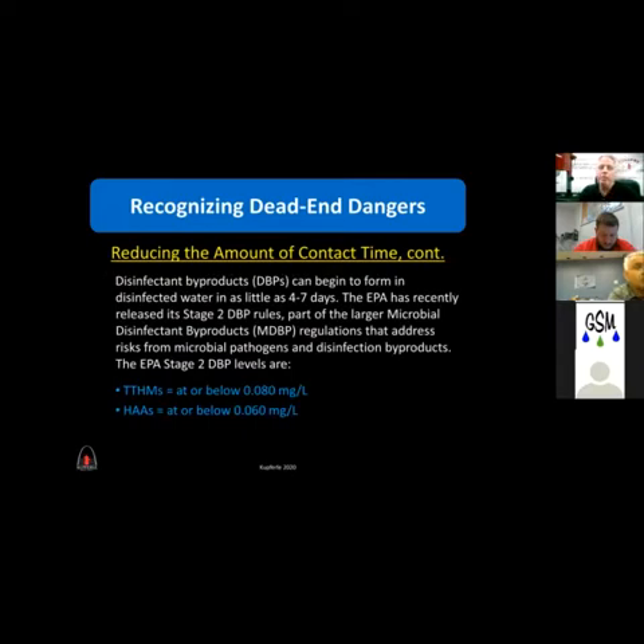Disinfection byproducts can start to form in about 4 to 7 days. So a good yardstick for water quality on a dead-end main is about 7 days or less. If my water is less than 7 days old, I'm probably not going to have a lot of disinfectant byproduct issues. If it's more than 7 days, I might start having these things form in my system.